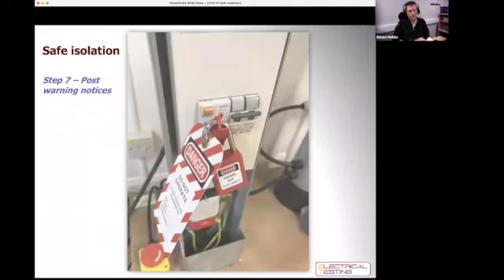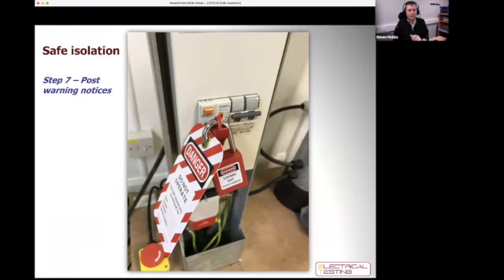The next step would be to post warning notices. These very much go with locking off the device, arguably could all be one step together. But just for this morning, to keep it nice and separate, we've put that there, that the warning notices need to be posted as well. May be able to see on the label there, typical things that would go on the warning notice would be the operative's name, maybe the company they're working from, a contact number, the date, which is incredibly important, and if need be, the equipment that's being isolated as well.